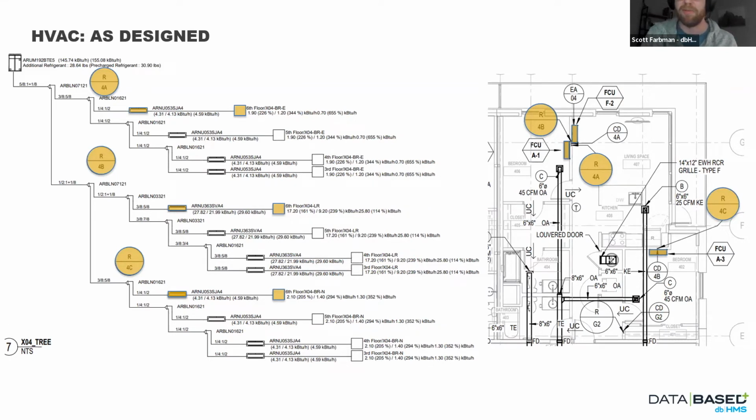So ultimately, we found it easiest to design and implement a vertical stack, and that's going to cut down on refrigerant lines as well, and then cut down on total refrigerant charge and load in the building, which is something that we're starting to pay close attention to now that we know that refrigerant is a pretty significant carbon emissions impactor. So we can move forward.